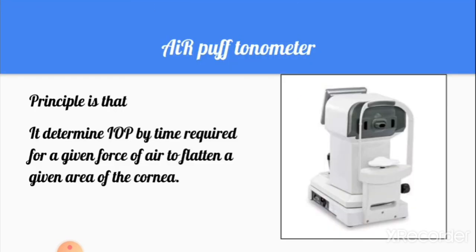The air puff (non-contact) tonometer determines IOP by the time required for a given force of air to flatten a given area of the cornea. The Tonopen is a digital tonometer — you instruct the patient to close the eyes, then place the tonometer head over the tarsal part of the closed eyelid, and it automatically records the IOP. Thanks for watching — please like the video and subscribe to the channel.